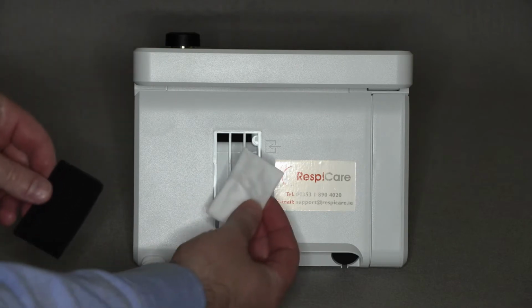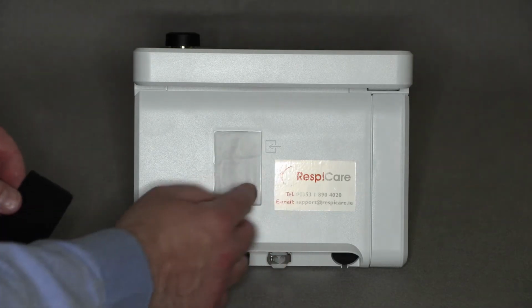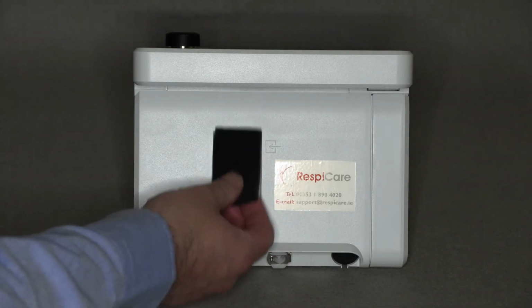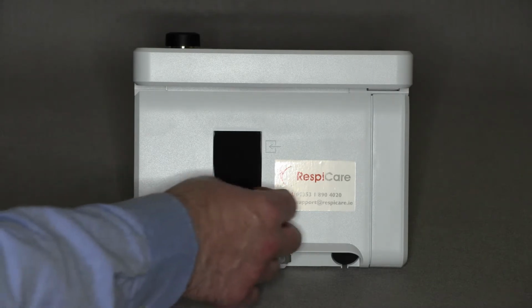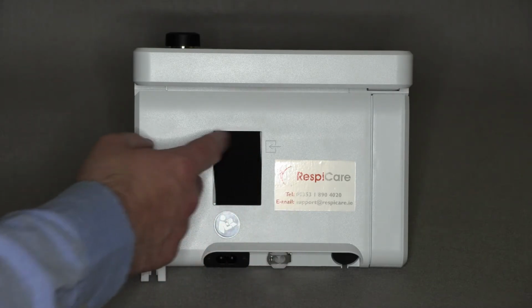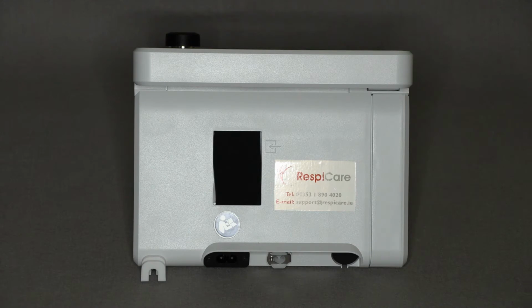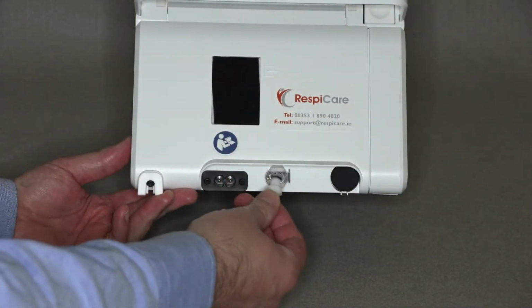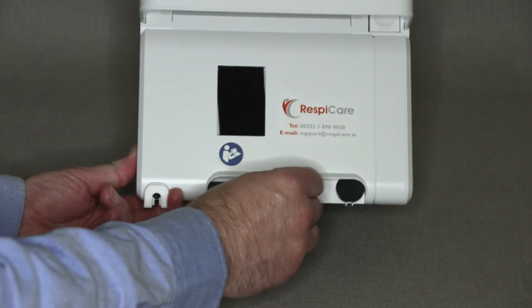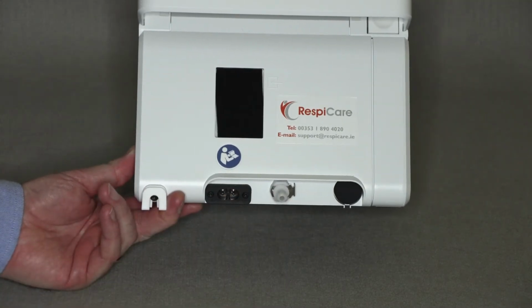For home use on a monthly basis, the air filter would be cleaned and reused when dry, and the pollen filter would be replaced. However, in the clinical setting, for the purposes of infection control, it's recommended to also replace each filter every time the ventilator is used with a new patient. The oxygen connector can be inserted into its connection at the rear of the ventilator by pushing it in fully and clicking it into place.